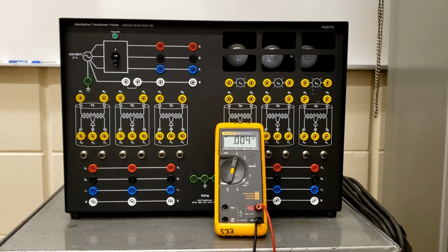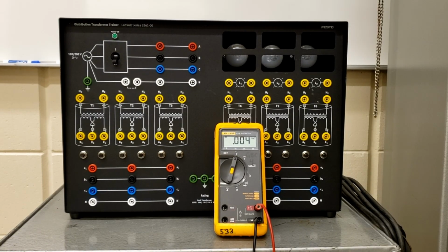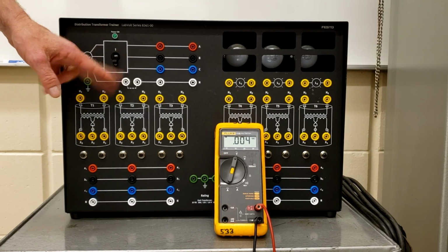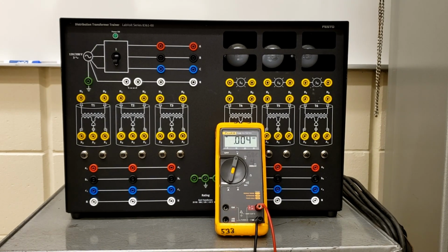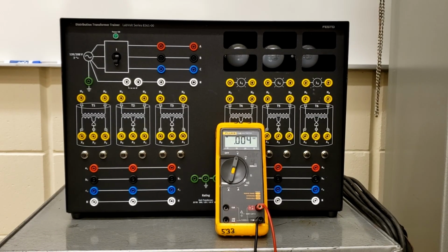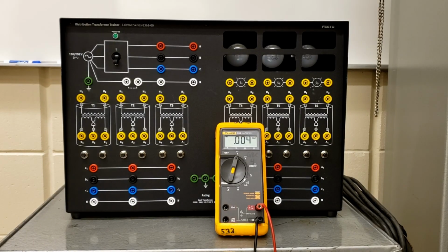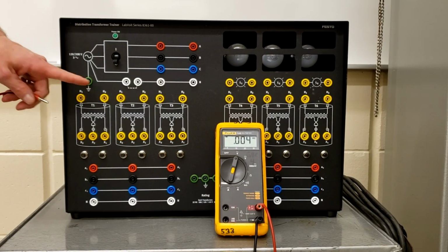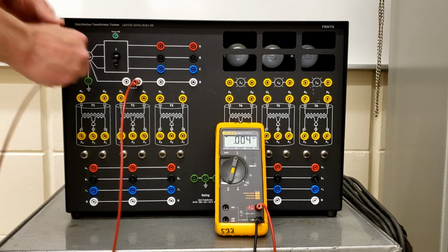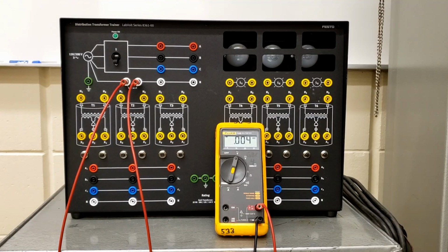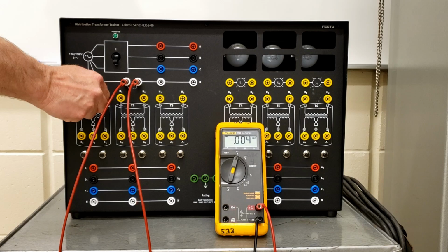Last one: Y to Y is 0 degrees phase shift, since we have a Y in the primary and a Y on the secondary. This diagram is on page 23 of the student manual, page 27 of the instructor manual. Looking here, it looks like we have all of our H2s tied together, and the question is whether you have to ground that neutral. Let's tie those together. We've got all of our H2s that need to be tied together to create that star point.